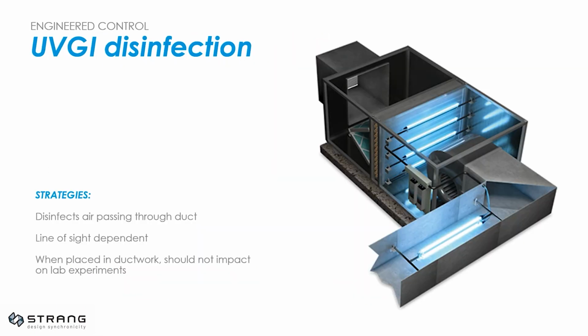In addition to simple HVAC adjustments, certain additive retrofits are also available. One additive option is the installation of ultraviolet lights within the air handling unit and ductwork. This is a relatively easy retrofit and serves to disinfect the air as it passes through the lights. This system treats the air that is introduced to a space but does not protect against direct person-to-person transfer within the space, which occurs throughout the workday.